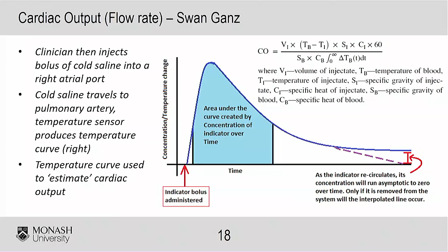Now, the area under the curve, of course, if you put a cold fluid into a system, into a loop, because you have to remember your blood circulation is a loop, eventually that cold fluid is going to make its way back up, and then you're going to see that small change again. In reality, you don't really see that kind of change because your body has auto-regulation of your temperature, so you don't really see that continuation of cold fluid. So we just kind of assume that the temperature drops kind of like this line, and then that's how we calculate it. So that's how, and I say estimate cardiac output here. It's a measurement, and it's the gold standard for measurement of cardiac output in patients, but it's still an estimation. We don't know exactly what the flow rate is coming out of the heart.